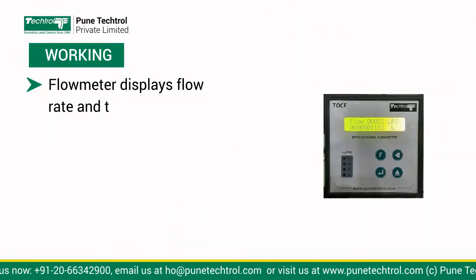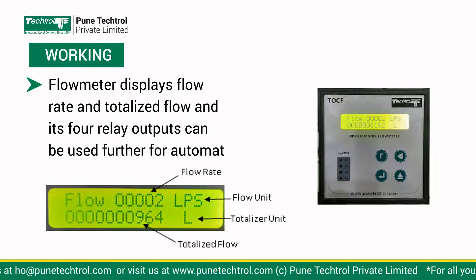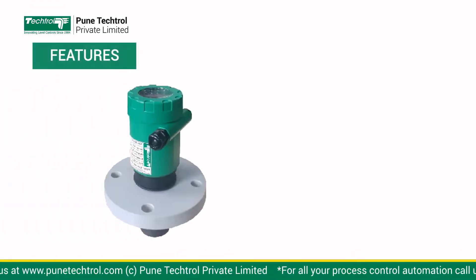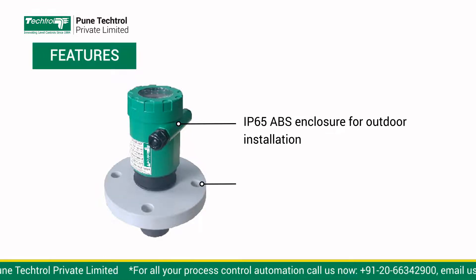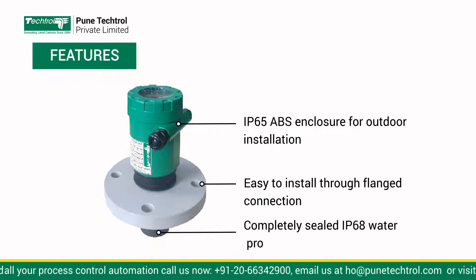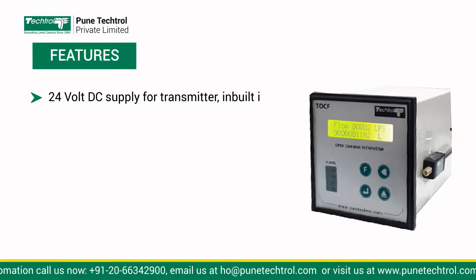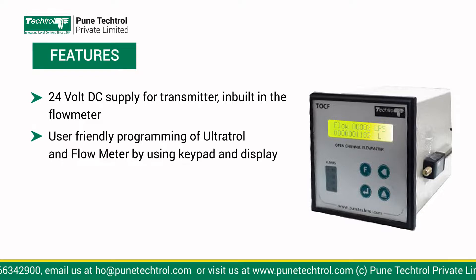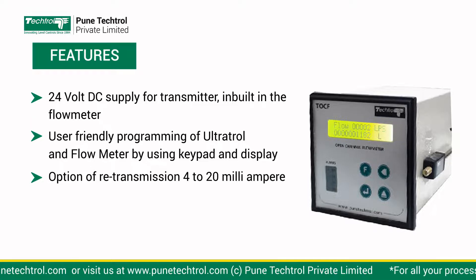The flow meter displays flow rate and totalized flow, and its 4 relay outputs can be used for automation. Features include an IP65 ABS enclosure for outdoor installation, easy installation through flanged connection, completely sealed IP68 waterproof transducer, 24V DC supply for transmitter built into the flow meter, user-friendly programming of Ultratrol and flow meter by keypad and display, and option of retransmission 4 to 20mA for remote indication.